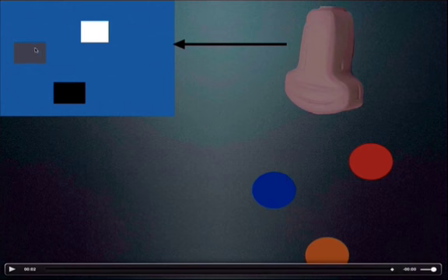whereas this reflector here was a weaker reflector, and it took a little longer for that signal to get to the probe. It returned to the probe at approximately this location. It's going to apply the pixel at this area of the screen, which is a little bit deeper from the surface. And then this reflector here really didn't return any sound at all, and we did not receive a return of signal in this area, so it just applies a black pixel. So let's watch that one more time.